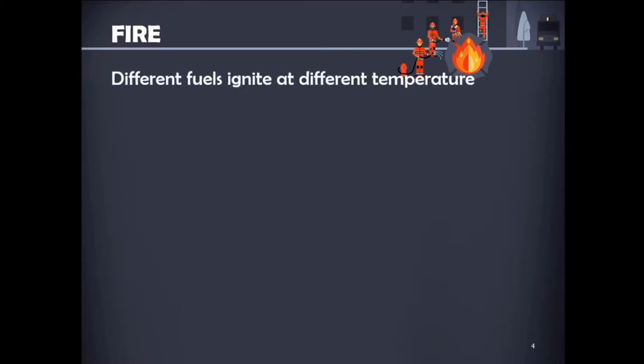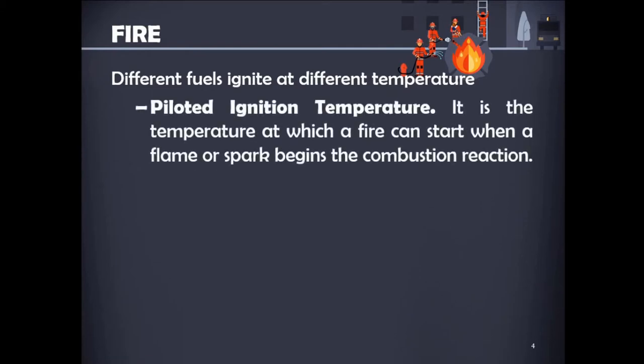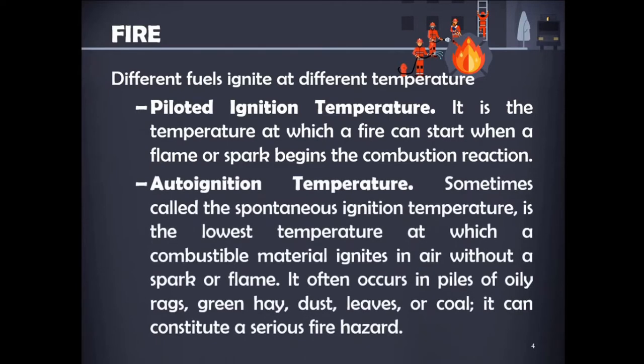Different fuels ignite at different temperatures. First is piloted ignition temperature — the temperature at which a fire can start when a flame or spark begins the combustion reaction. The fuel is hot enough that it releases sufficient flammable gases for combustion to occur, but a catalyst is needed to begin ignition. Second is auto-ignition temperature, sometimes called spontaneous ignition temperature — the lowest temperature at which a combustible material ignites in air without a spark or flame. It often occurs in piles of oily rags, green hay, dust, leaves, or coal, and can constitute a serious fire hazard.